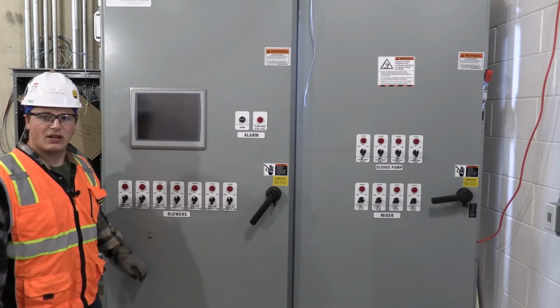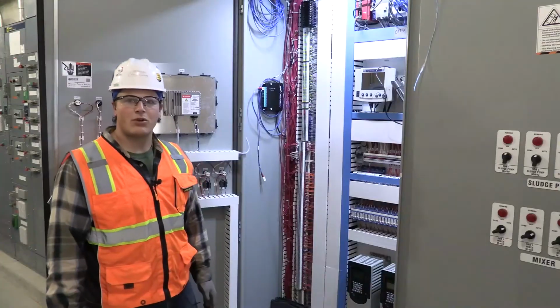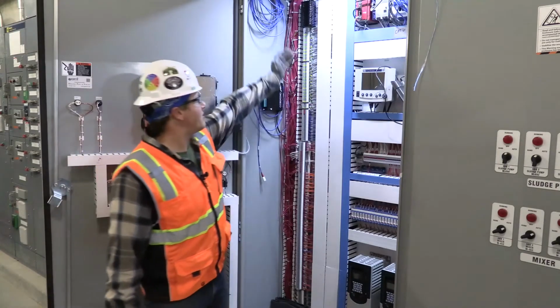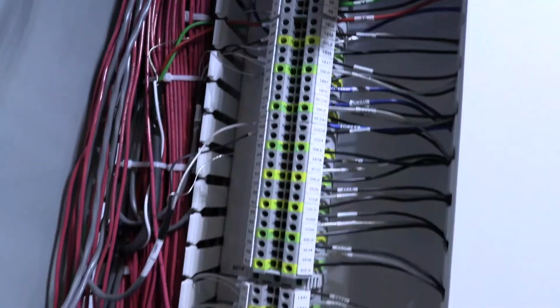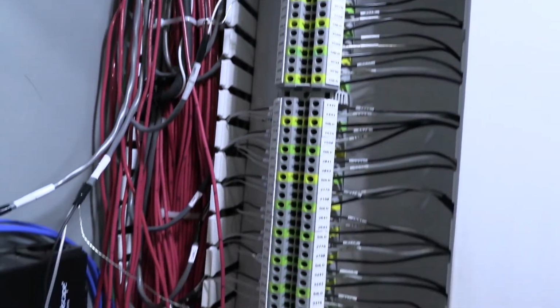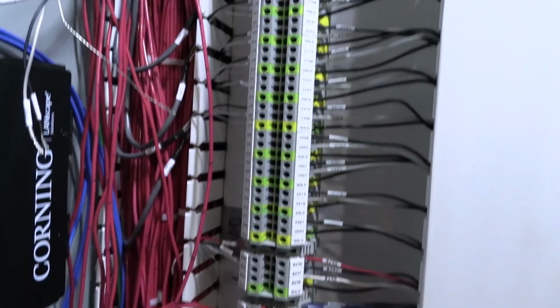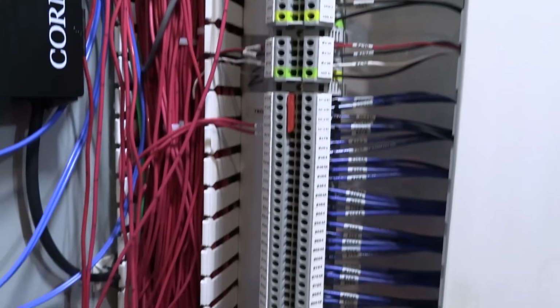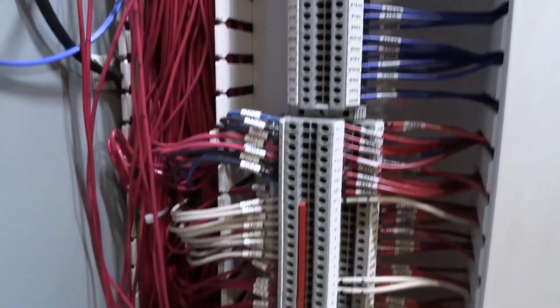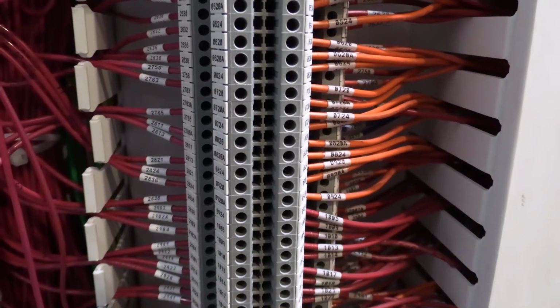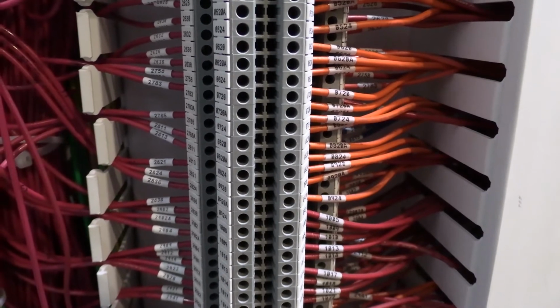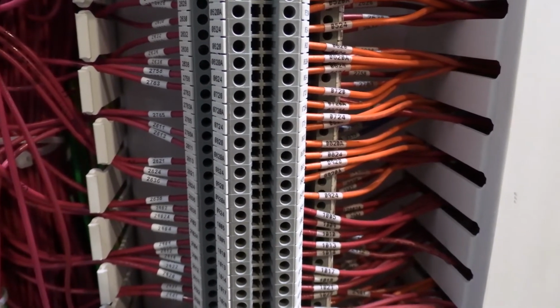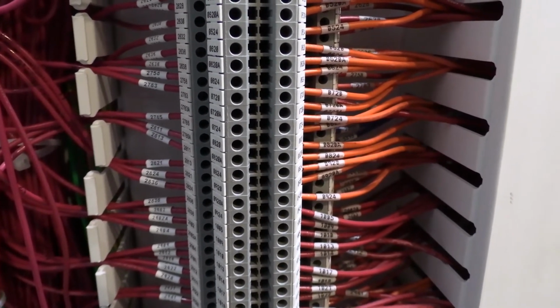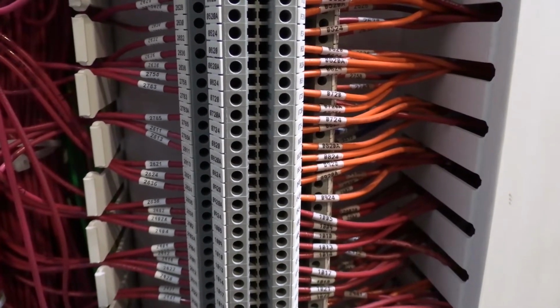There are quite a few pictures that are required to be sent to the service coordinator to confirm correct installation. The majority of our panels have field terminations on the left side. You will need a minimum of 2 pictures of these field terminations for the electrical engineer and service coordinator to review. This is an example of a double-stacked field termination block. Make sure your pictures clearly show the numbers on the bottom and the top.